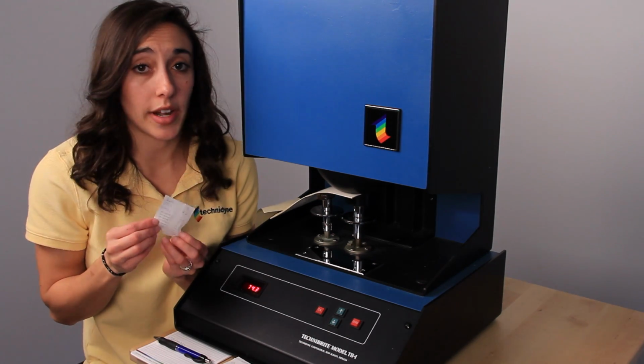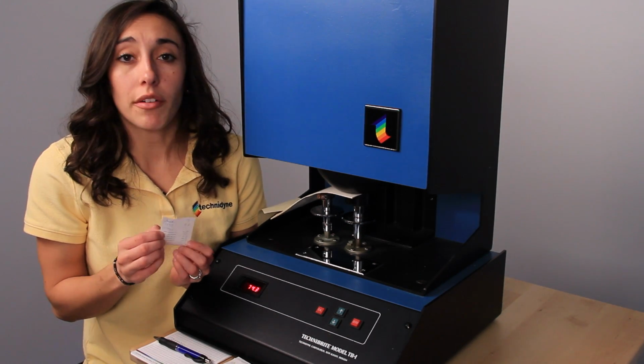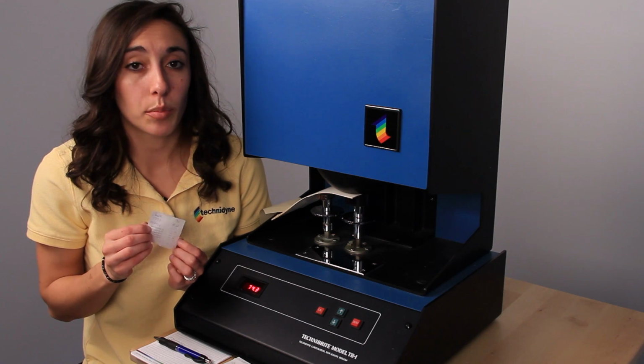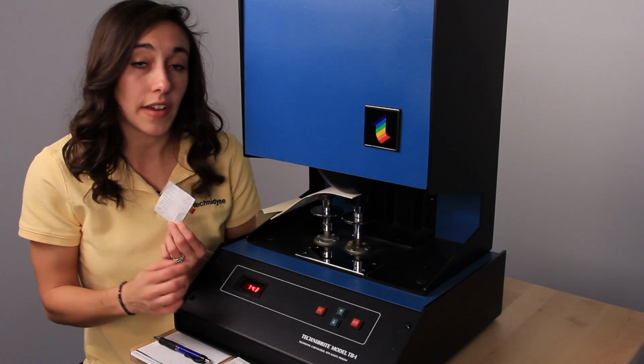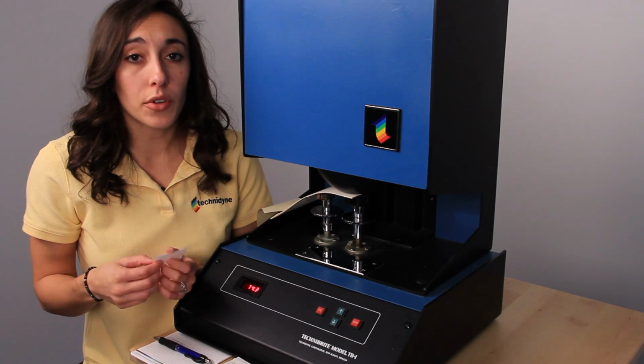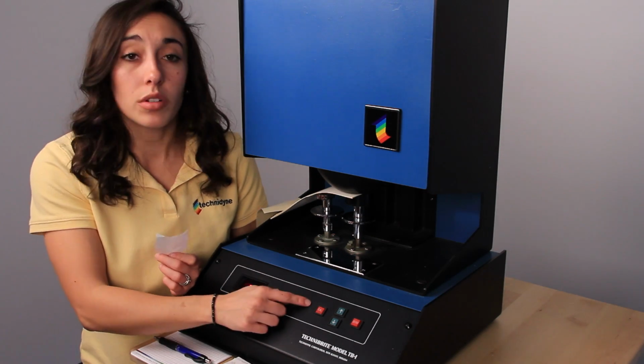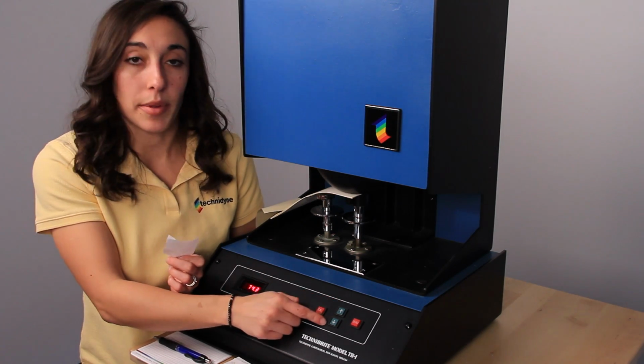Now, if you look at the printout for the 70 standard, you'll notice that that very first brightness value probably doesn't quite match the value on the display. In order to get those numbers equal, we'll hold down the Calibrate button and use the up and down arrow keys.